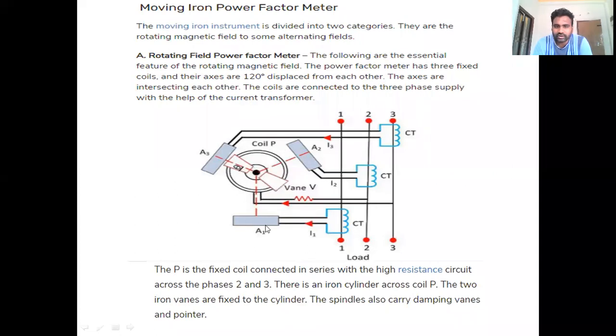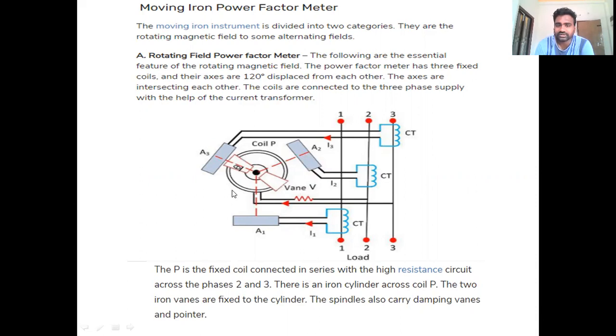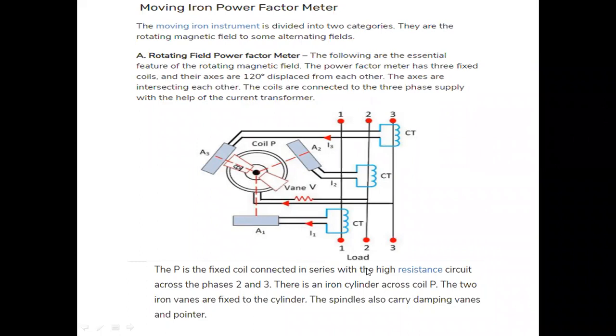In summary: three field coils A1, A2, A3 are placed at 120 degrees displaced from each other. A moving coil is placed between the three field coils, and a vane system is attached to a spindle on the coil. After the rotating magnetic flux is created by current injection to the three coils, the vane system and coil start rotating — the rotation depending upon the current injection, which in turn depends on the voltage and current relationship of the three-phase system.